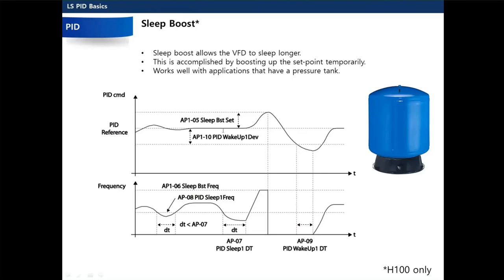Okay. What it's going to do is boost up your set point by whatever you program into the drive, and then it's going to go to sleep. It overpressures the system, pulls up your pressure tank a little bit, and then it goes to sleep. And what that does is it allows you to sleep a little bit longer. That way you have less oscillating, less turning on and off, a little bit less wear and tear on the pump and the motor and all the mechanics associated with it. That's why people would use a sleep boost. Available only on the H100.